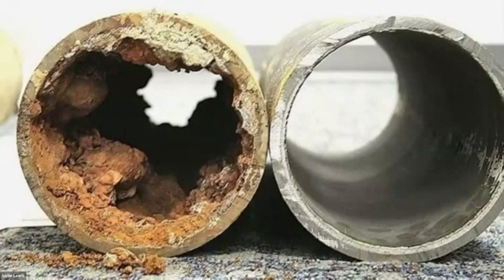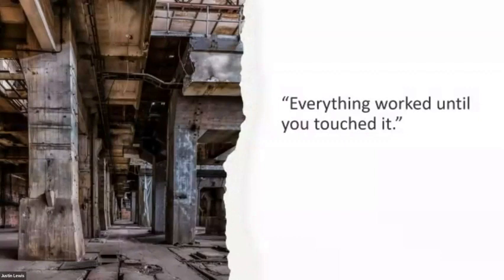How many times have we dug into an underperforming water system on an existing system and found this? Design teams may assume ideal conditions that don't really exist. This can dramatically affect the system performance down the road. Not only is it important to identify limitations so that the design team has all of the information they need, but the construction team needs to understand and document existing conditions as well. It doesn't matter how poor of a condition the system is in, if they were not verified beforehand and documented, the construction team owns it. Why? Because everything worked until you touched it.